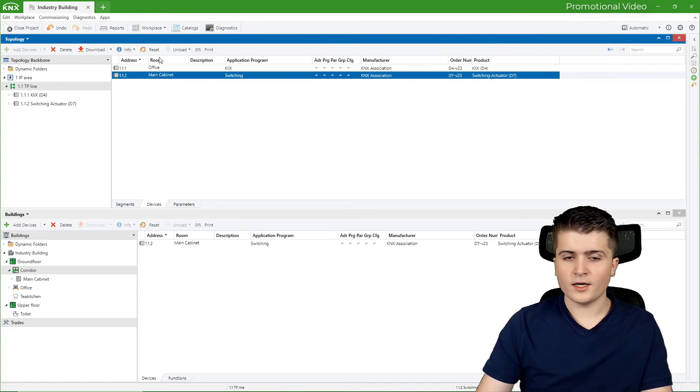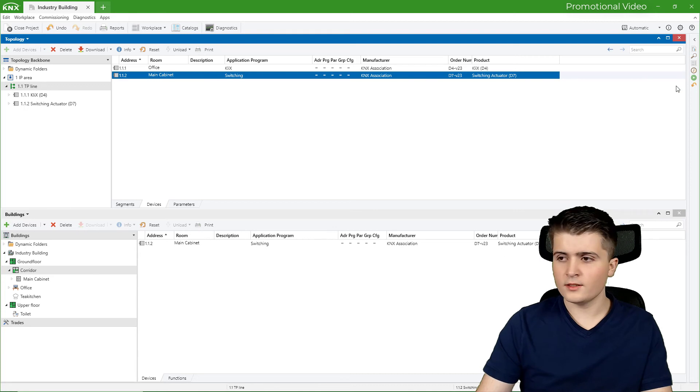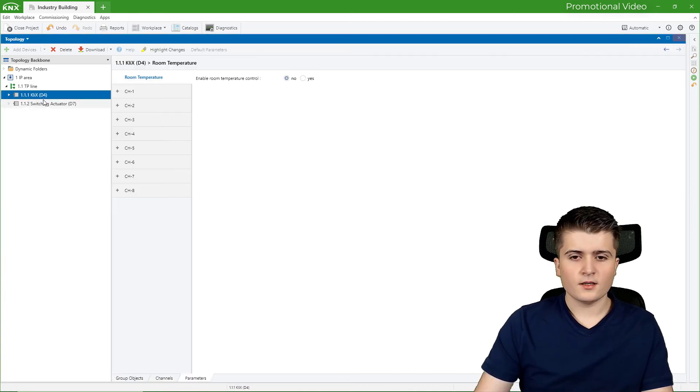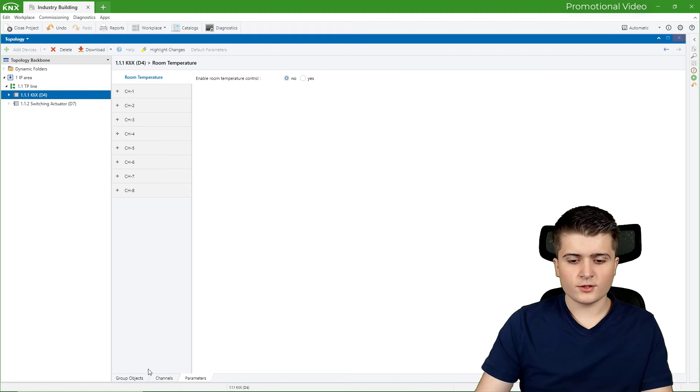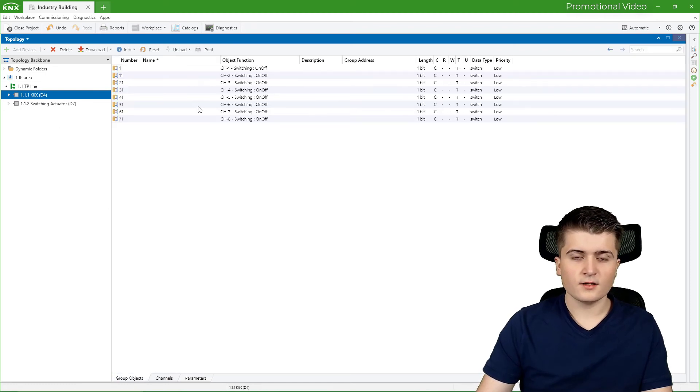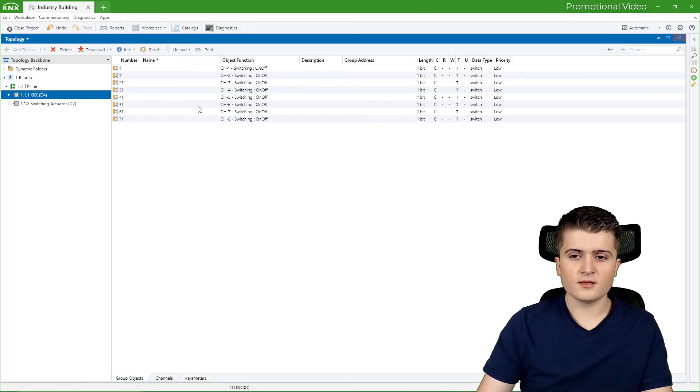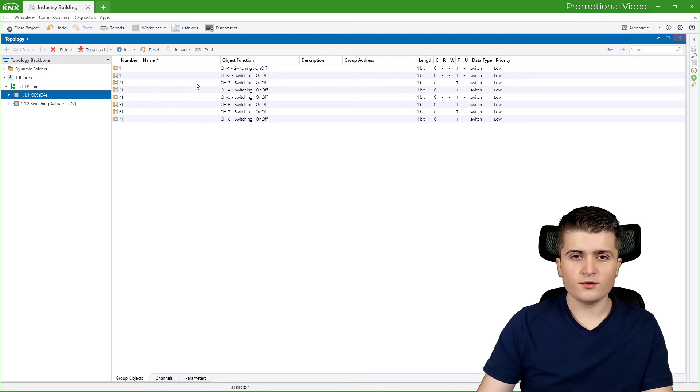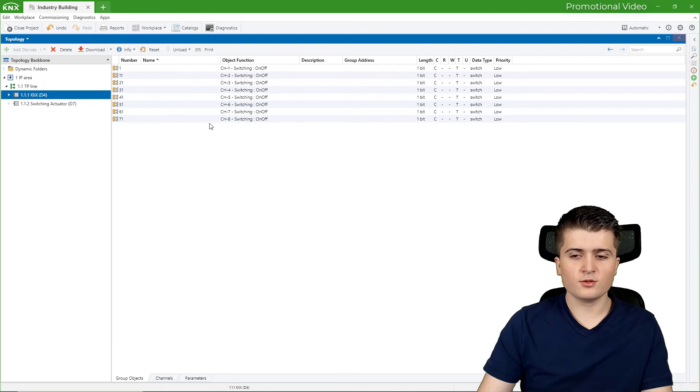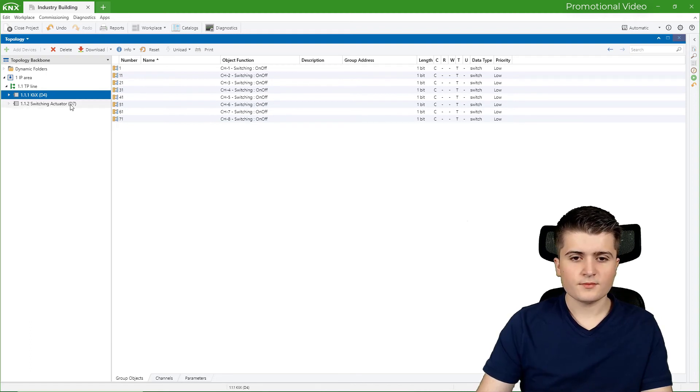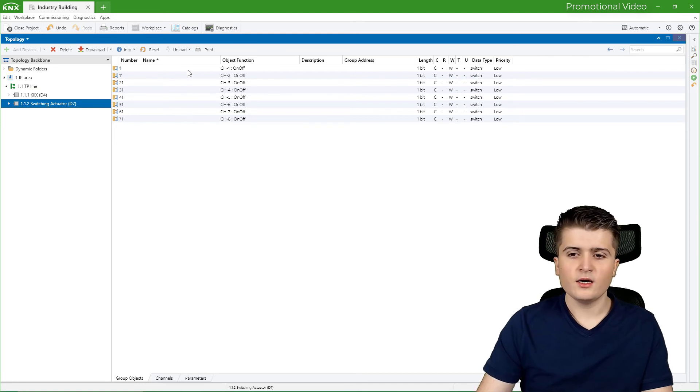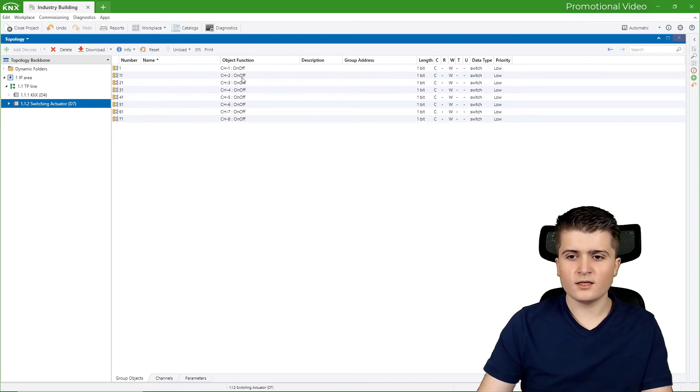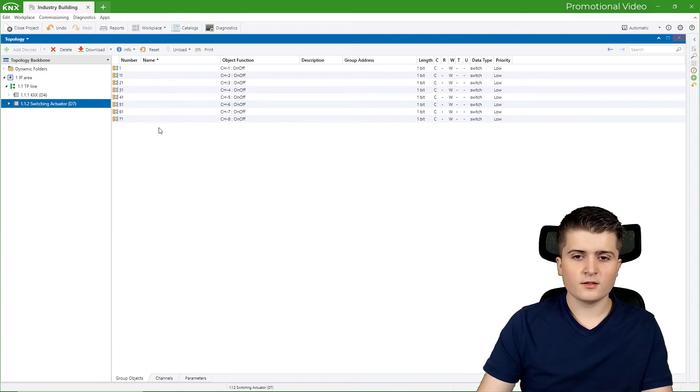Therefore I can either close topology or building, which way you prefer to work. And now if we take a look at the push button sensor, so the clicks, you can already see the group objects this device has. So here in this case we have an 8 fold push button sensor. Therefore 8 group objects with a switching on off function enabled. And in the switching actuator, the same thing. There we have 8 channels which we can use for switching. And therefore we have 8 group objects for now.